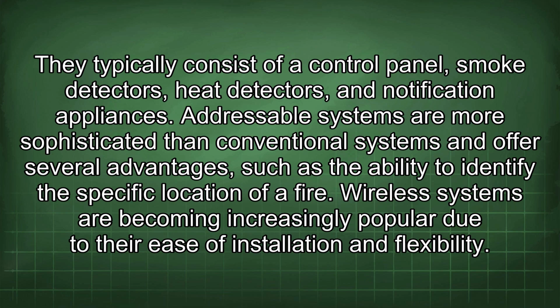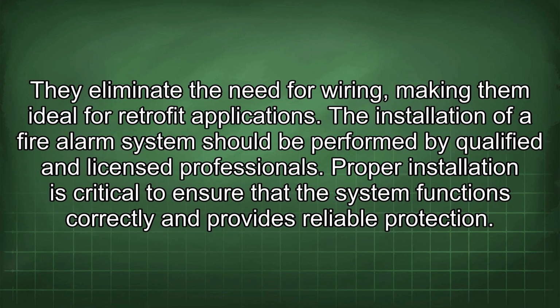Addressable systems are more sophisticated than conventional systems and offer several advantages, such as the ability to identify the specific location of a fire. Wireless systems are becoming increasingly popular due to their ease of installation and flexibility. They eliminate the need for wiring, making them ideal for retrofit applications. The installation of a fire alarm system should be performed by qualified and licensed professionals. Proper installation is critical to ensure that the system functions correctly and provides reliable protection.